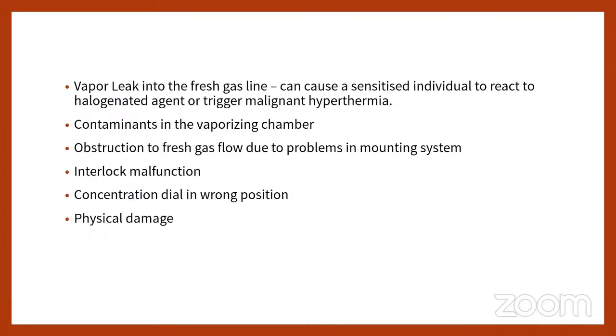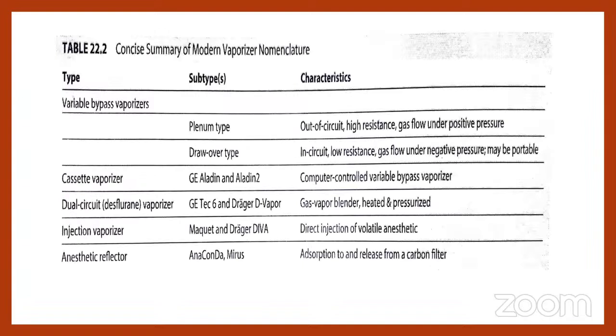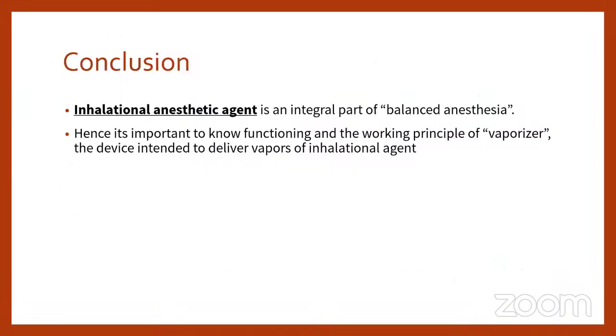Vapor leak into the fresh gas line can cause sensitivity to halogenated agents or trigger malignant hyperthermia. Other hazards are contaminants in the vapor chamber, obstruction to fresh gas flow due to problems in the mounting system, interlock malfunctioning, concentration dial in the wrong position, and physical damage. These are the various hazards that can be seen while using these modern vaporizers. This is the summary of various vaporizers, their types and the characteristics of each vaporizer.